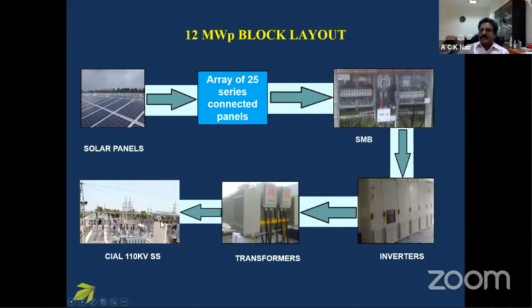This is the 12 megawatt power plant block layout: solar panels in arrays of 25 series-connected panels with string monitoring boxes, then inverters, then transformers. From the transformers, it converts to 11 kV power, which feeds to the Cial 110 kV substation that connects to the grid.